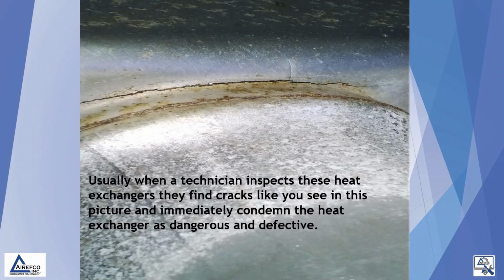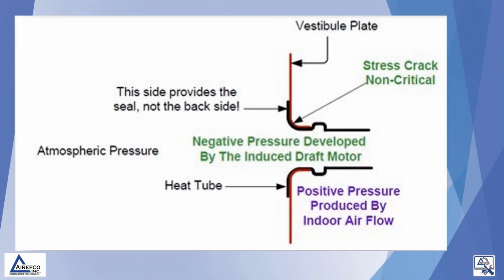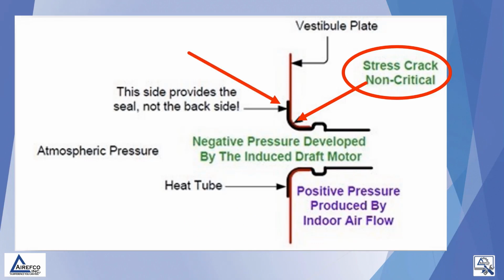Usually when a technician inspects these heat exchangers, they find cracks like you see in this picture and immediately condemn the heat exchanger as dangerous and defective. A number of years ago, Carrier released this diagram of how these heat exchangers are put together, showing that the stress crack or the cosmetic crack is non-critical as it is on the other side of the seal that is developed on the back side of the heat exchanger by the plate on the back side.